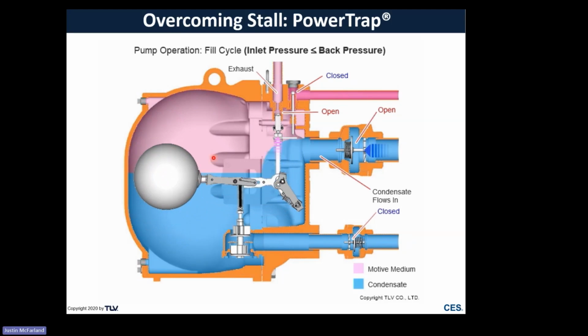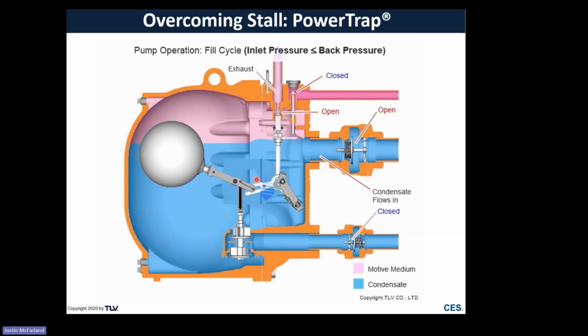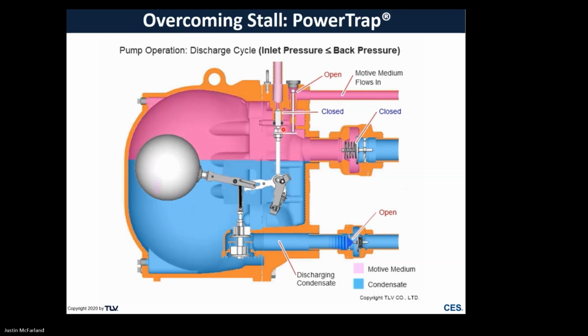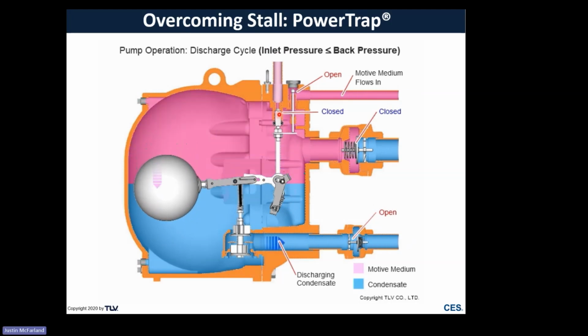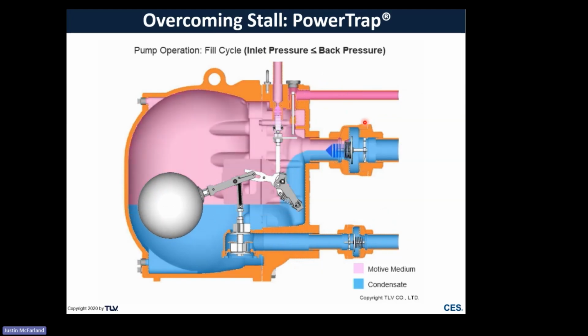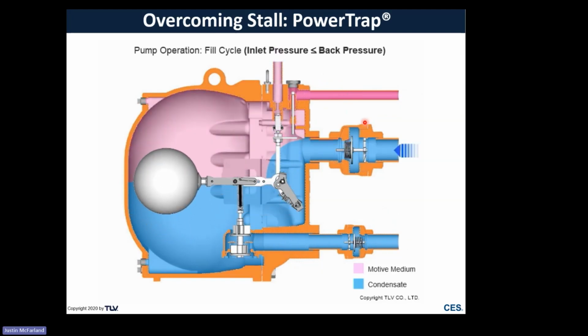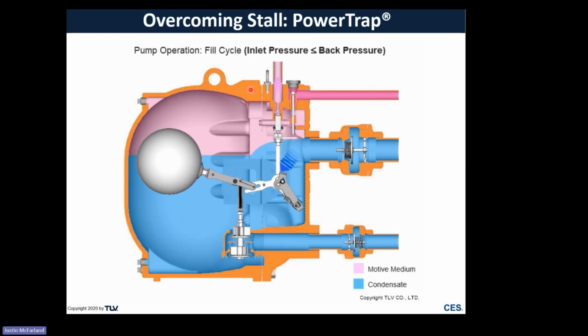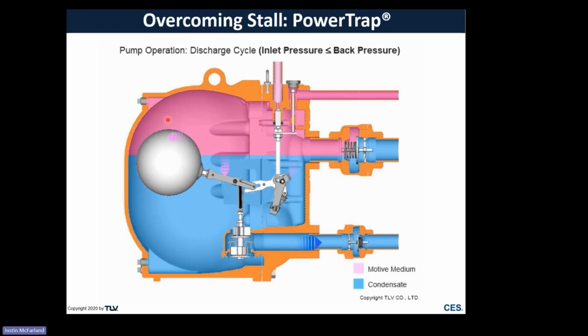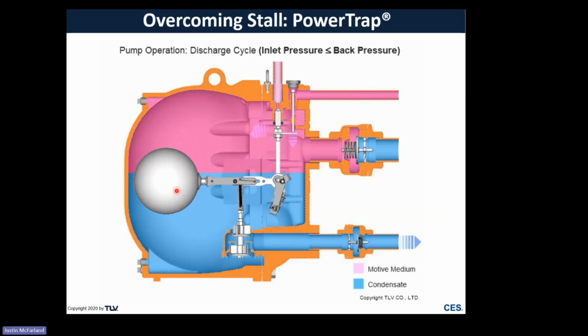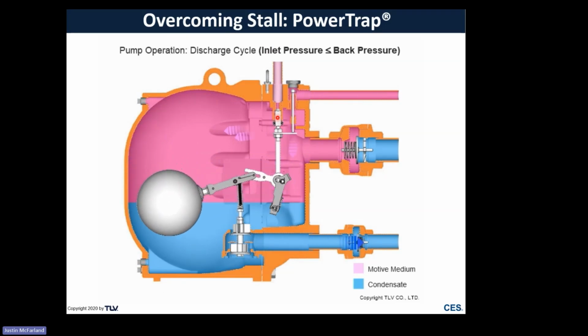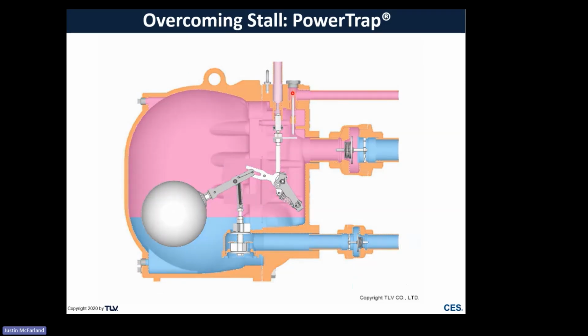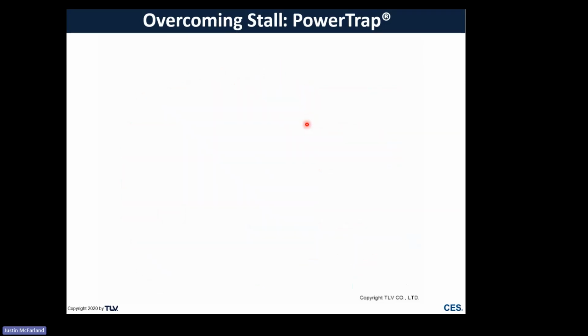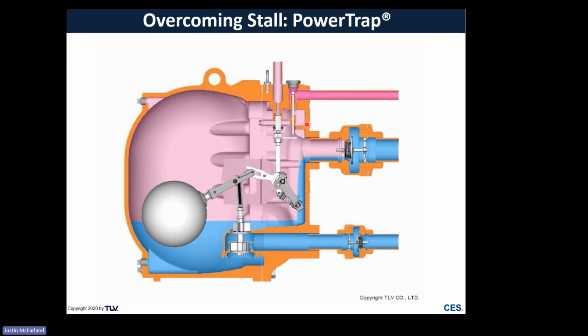We get to a high limit here. It's going to engage a snap action mechanism. And you'll see that this valve for the exhaust closes. This valve for the motive line opens and fills the pump body and begins pressurizing the pump body to push it out. As soon as it gets down to the low limit here, it's going to re-engage these, open up the exhaust, close the motive valve, and exhaust that back to the rest of the system.